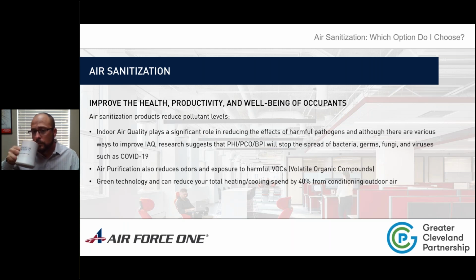Very specifically, when you're using whether it's a BPI, needlepoint BPI, PHI, or PCO, and you're going to use it in a fashion where you reduce outside air, the one important caveat is—and most newer buildings will have this, but older buildings will not—you need to still have CO2 demand ventilation, because that's the one item none of these technologies address: CO2 levels in the space. So we'll touch on that a little bit later, but it's very important to note that you can add that when you do the air sanitization technology, but you have to have that to reduce outside air. Thanks, Brian.